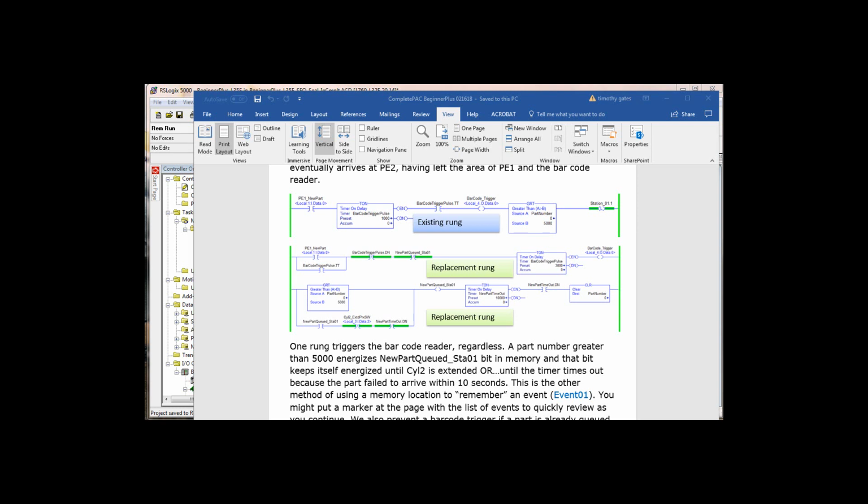So you could even jumble, move around the rungs in a different order and it would still run okay. Seal-in logic is, and you know this from volume 1 where you did latch and then you did seal-in logic, that everything that controls that output bit, whether to set it or clear it, is all in one rung. Easier to troubleshoot, a little bit more difficult to write.